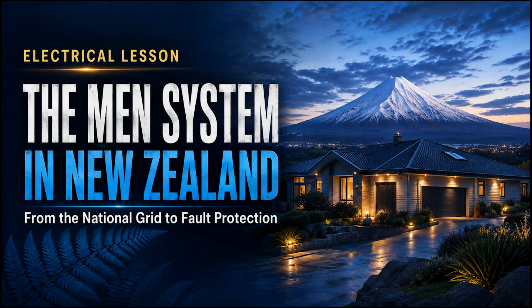It also allows exposed conductive parts in an installation to be connected back to that Earth neutral through the protective earthing system. But the neutral is not earthed at only one place. It is earthed at the source, at regular points in the distribution system, and at connected electrical installations. That is why the system is called multiple earthed neutral.